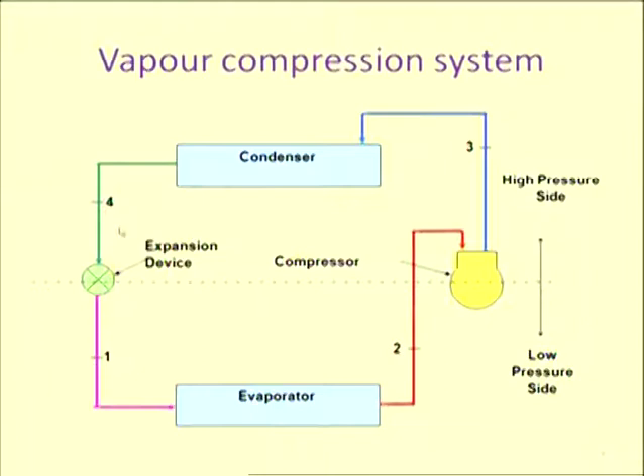So after expansion, here you can see this is a high temperature region, over this dashed line, and this is a lower temperature region. So these two components are maintained at a lower pressure, and these two components are maintained at a higher pressure. So this is the low pressure side and this is the high pressure side. So after the expansion in the expansion device, the saturated liquid coming out from the condenser is expanded and will be in the phase of low temperature, low pressure, wet vapor.